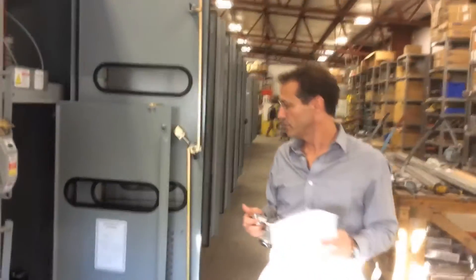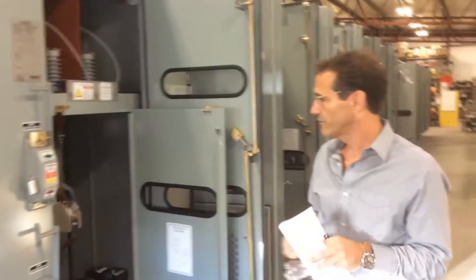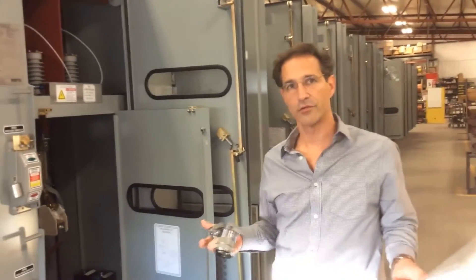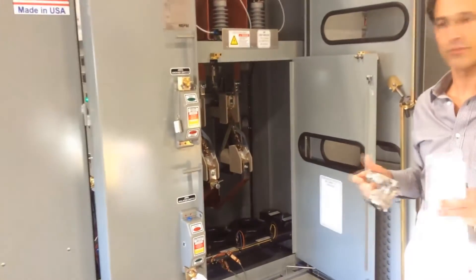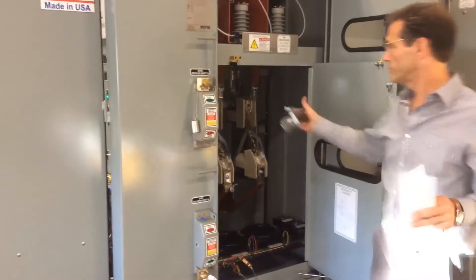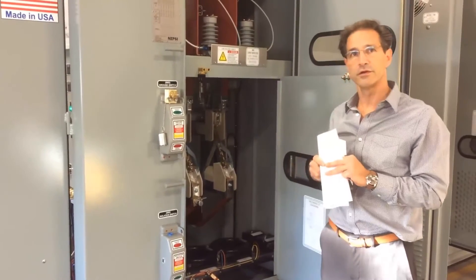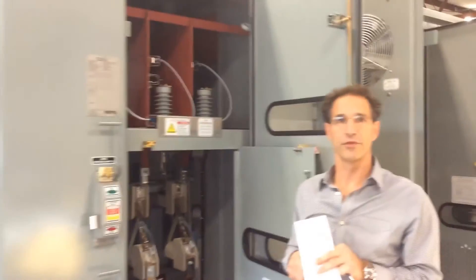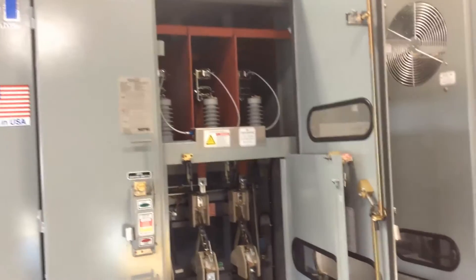Just some other points to note, since we're on the subject of arc flash mitigation: arc flash mitigation also involves trying to prevent faults from occurring and trying to prevent errors from occurring. We have key interlocks to prevent out-of-sequence operation of the equipment, which would prevent the ground switch from being closed on a live bus. We also have current limiting fuses in the incoming compartment to reduce both the magnitude and the duration of any internal faults within the equipment.